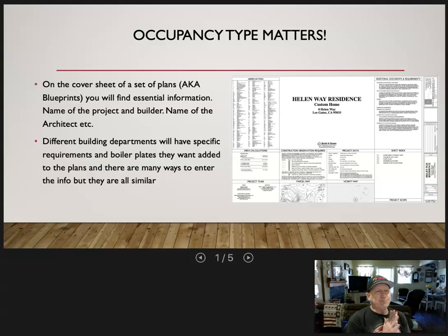It's something that when we go out and do fire inspections, we really want to be paying attention to: is the occupancy type that the building was built for still the way it's being used? Because a lot of times, especially in rental buildings, big businesses, big warehouses, one person goes out of business and leaves, another one comes in, and we have a different occupancy type.